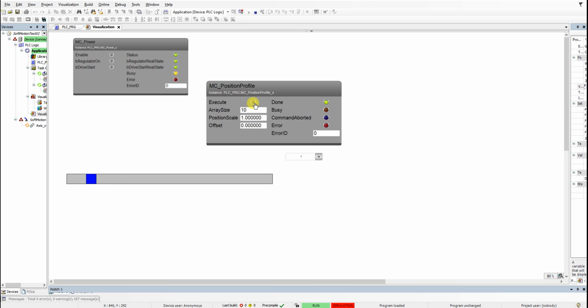Now you should see the difference. Let me make it 0. The movement now refers to the first one. If I make it 1, we will have the relative kind of movement. It goes forward and backward, and then after the selected number of the time position elements used, the drive will stop.